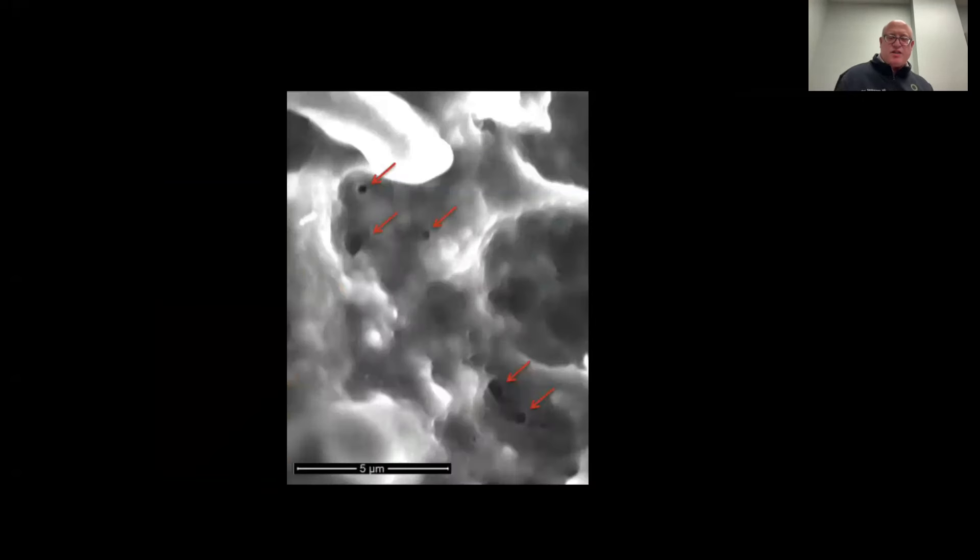This is relatively new technology. The time course of these lesions is not four seconds, but is measured in nanoseconds, and the current is rapidly on-off with each heartbeat for just a few heartbeats, and the lesion is complete.